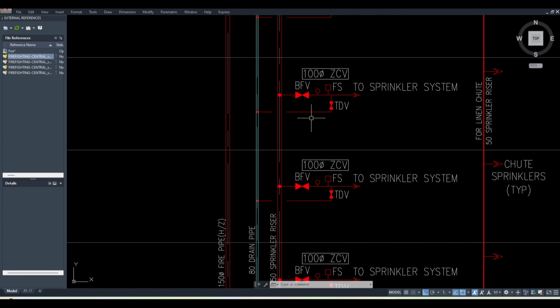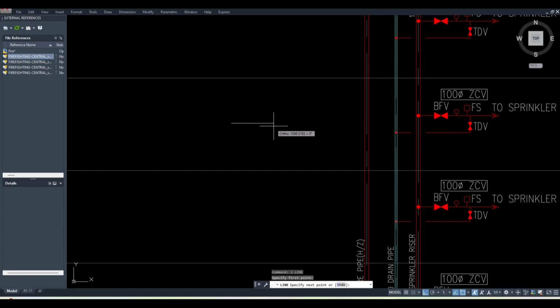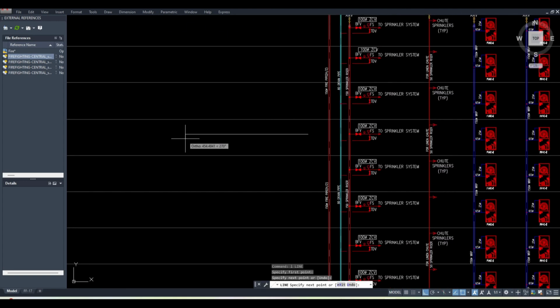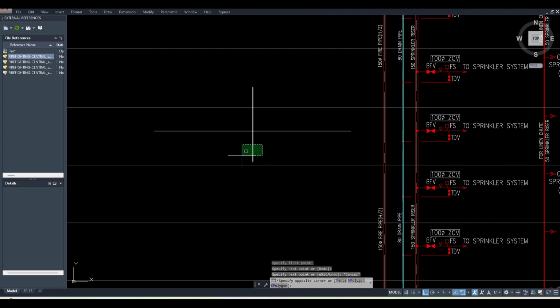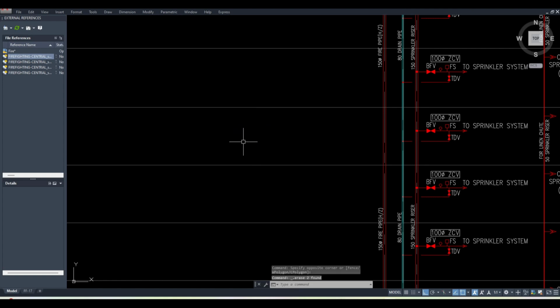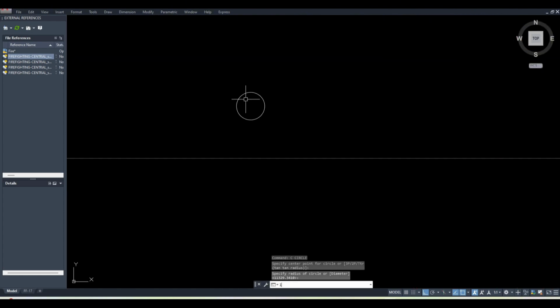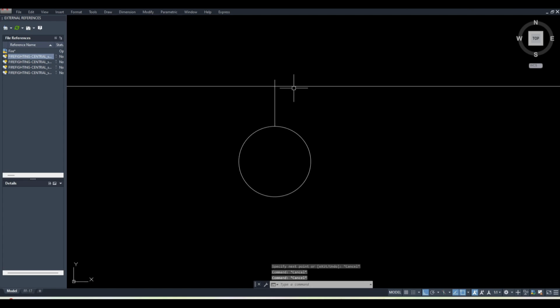Okay. Now the other thing is, when we make the sprinkler pipe, let's say from the zone control valve one pipe is coming like this. Okay, and then this is like this. So the branch pipe, this we call the branch pipe, and this is, let's say, the main pipe. So when the connection is happening with this main pipe, I will draw a section here. The connection should be in such a way that, let's say, this is a sprinkler main pipe. Then the branch pipe, you take it like this up, and then again you take it like this. So what is the benefit of this? Two benefits you will get. I will explain to you. So first benefit, what will you get?